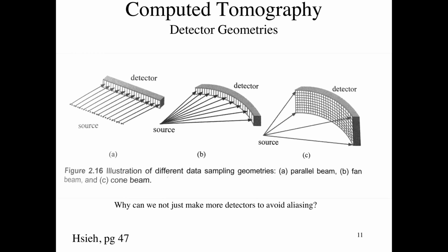In a parallel beam situation, if I have an X-ray emitter here and I blast X-rays this way, and I have a single detector here, I can just raster that single detector across while I'm taking my data. Right, so I really only need one detector. And at that point, you're just integrating X-rays over time, stopping, storing that number, integrating some more, stopping, storing that number.